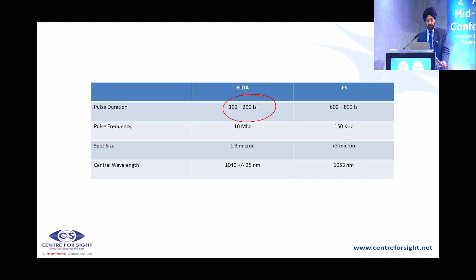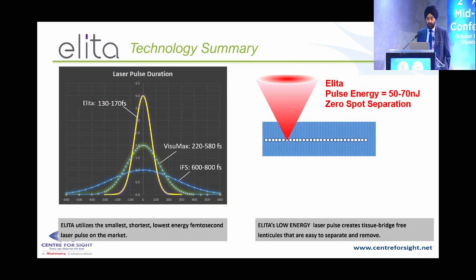Comparing ELITA with the IFS: pulse duration has gone down to an average of only 150 femtoseconds — the shortest pulse available. Pulse frequency is very high at 10 MHz, spot size only 1.3 microns, wavelength 1040 nm. Comparing with VisuMax 500 and IFS, the pulse energy in ELITA is significantly the lowest of any system — only 50-70 nanojoules — translating to less collateral tissue damage.